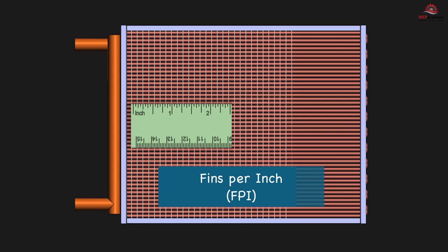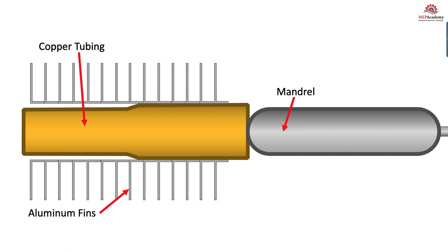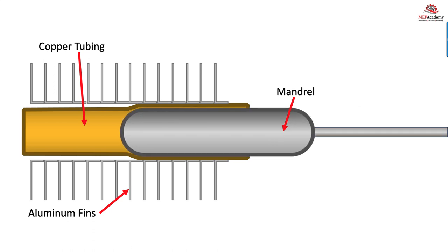Coils can be provided with anywhere from 4 to 20 fins per inch. Increased surface area — meaning more fins per inch or more rows — will increase the heat transfer capabilities, but at the cost of fan energy. Coil manufacturer's software will pick the best coil with the least number of rows to meet the project requirements. The fins are attached by forcing a mandrel through the copper tubing, causing the tubing to expand and tighten against the fins. This ensures a good bond between the tubing and the fin, which creates good thermal conductance for heat transfer.